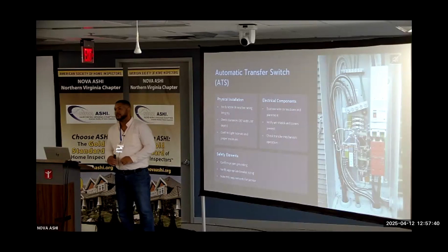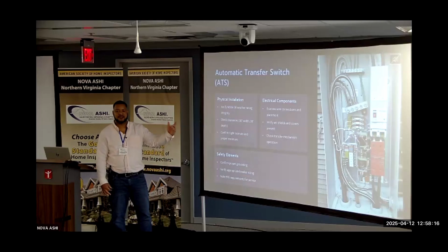Another thing that I suggest and recommend: are you guys looking to test generators to tell the homeowners it works or it doesn't work? No? Okay. Well, just in case you did, in this instance, what you would do is turn off that 200 amp breaker, which would simulate losing the utility power. The generator would sense the loss of voltage and start up, and once it gets to the proper usable voltage, the transfer switch would transfer over, and now you would have generator power. You could actually do that test there, just by turning that off.